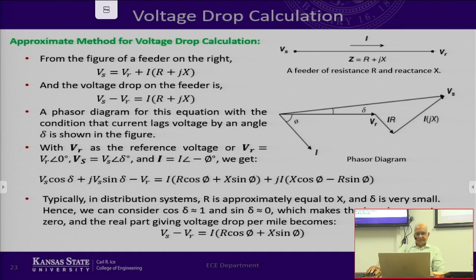Okay, and then what we're going to do is calculate the voltage drop in percentage, voltage drop per mile, because the assumption is the load is balanced and all the phases have the same impedance. I told you in the beginning that we're going to assume that to be the case. And then you have voltage drop as R cosine phi plus X sine phi. Now, this is on a per phase basis. We are looking at each phase.